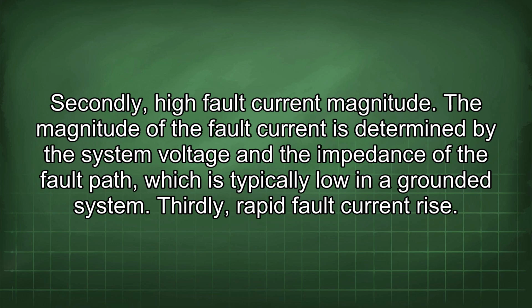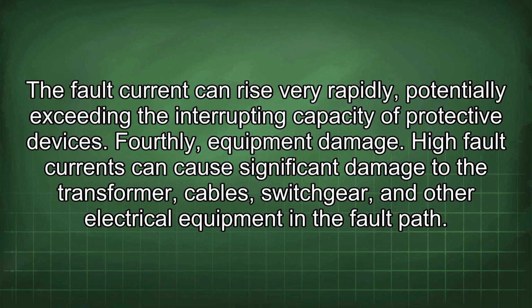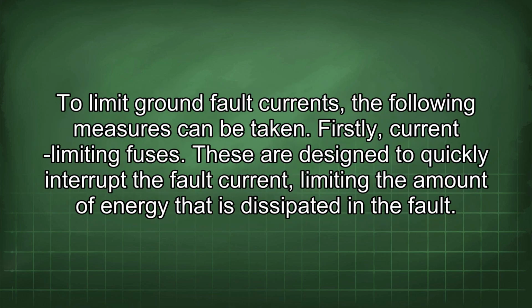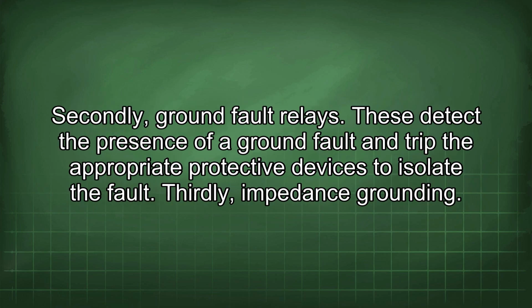Thirdly, rapid fault current rise. The fault current can rise very rapidly, potentially exceeding the interrupting capacity of protective devices. Fourthly, equipment damage. High fault currents can cause significant damage to the transformer, cables, switchgear, and other electrical equipment in the fault path. To limit ground fault currents, the following measures can be taken. Firstly, current limiting fuses. These are designed to quickly interrupt the fault current, limiting the amount of energy that is dissipated in the fault. Secondly, ground fault relays.